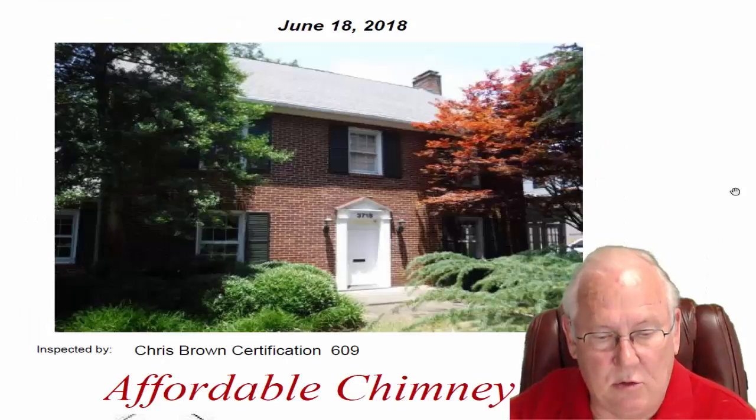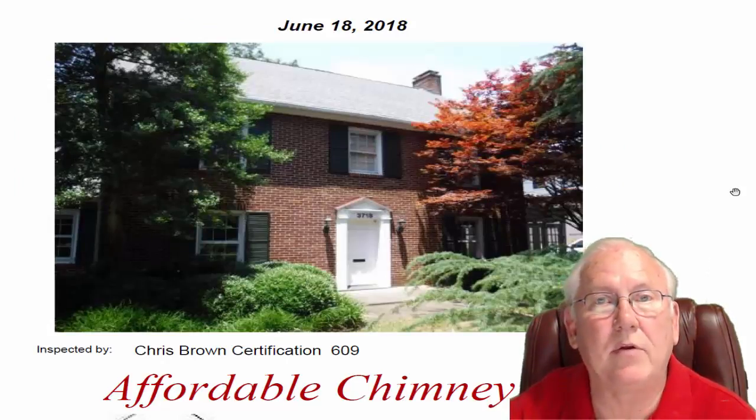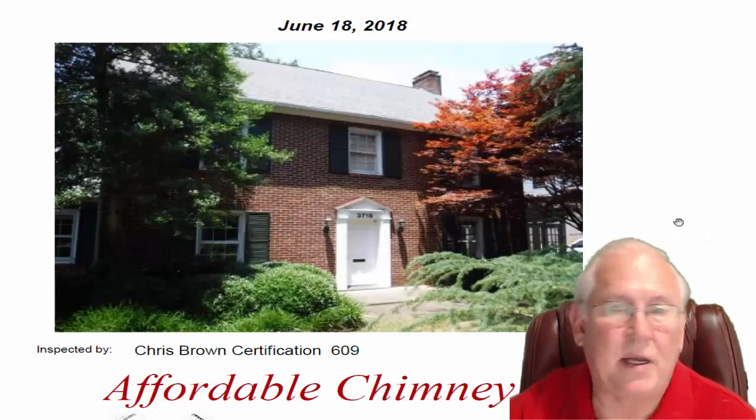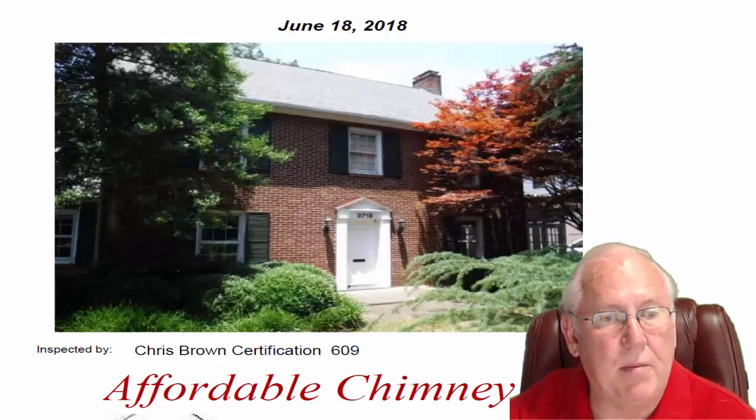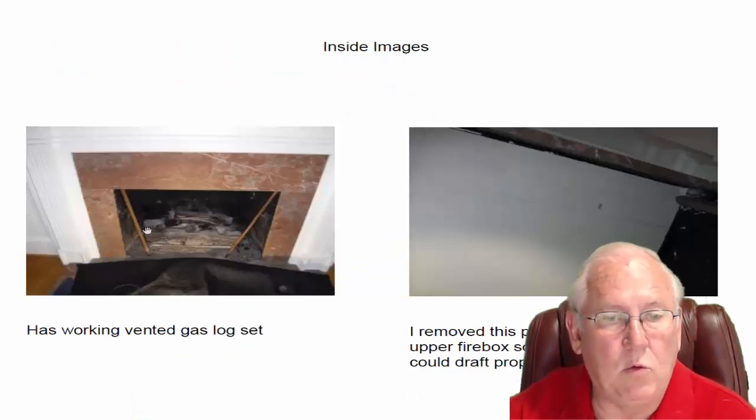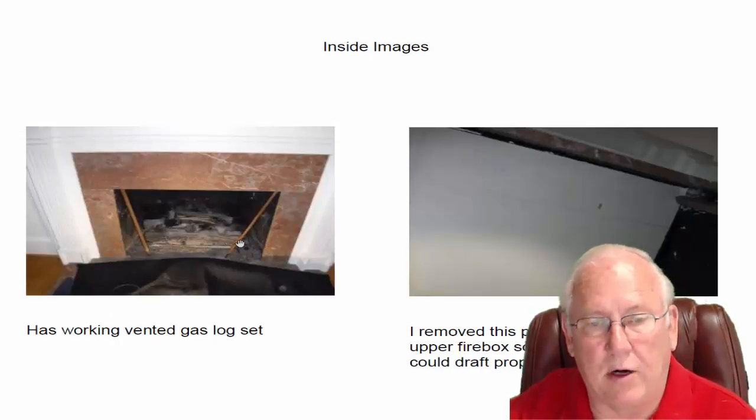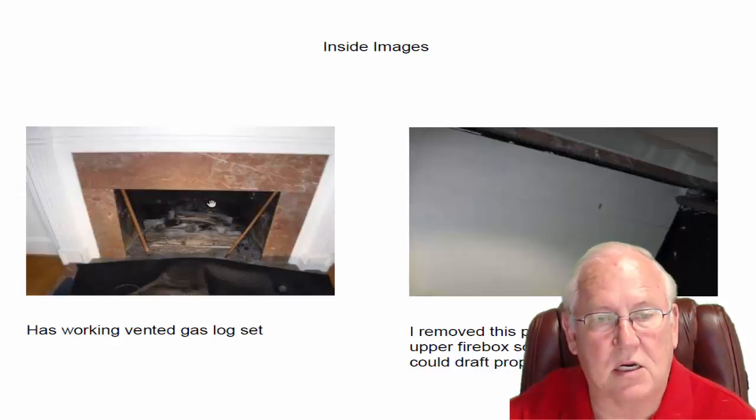Hey, Bobby. We went out to the house over on Selwyn Avenue and cleaned and inspected the chimney for you. I want to go over these pictures with you, if I may. Open wood-burning fireplace, of course, but it has vented gas logs in it. They've got a piece of sheetrock just kind of stuck up in there with these sticks holding it.